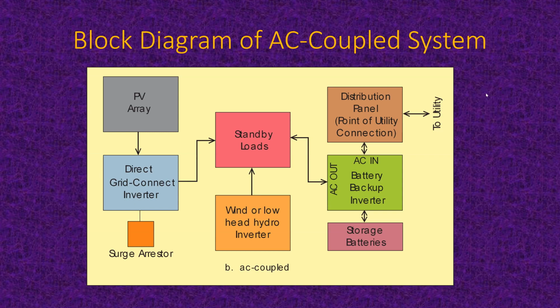Okay, so here's the AC coupled system. The first thing to notice here is there's two inverters. Now, one nice thing about this is that you may have started a system with an array on the roof and a direct grid connect inverter that connected to your main distribution panel and fed loads there while the sun was shining. And anytime the sun wasn't shining, it was up to the utility to supply those loads. But if the utility was gone, then you were out of business. There was no backup because the UL 1741 thing says if the utility is down, the PV has to shut off. It can't connect to the utility anymore.